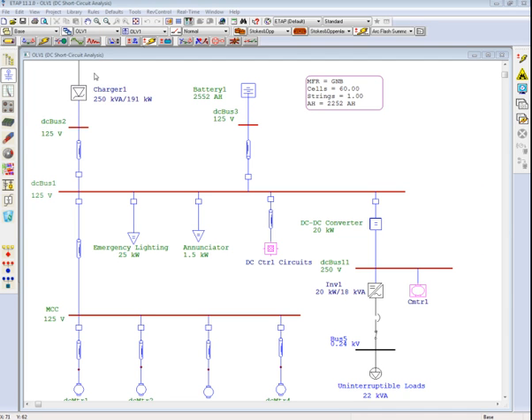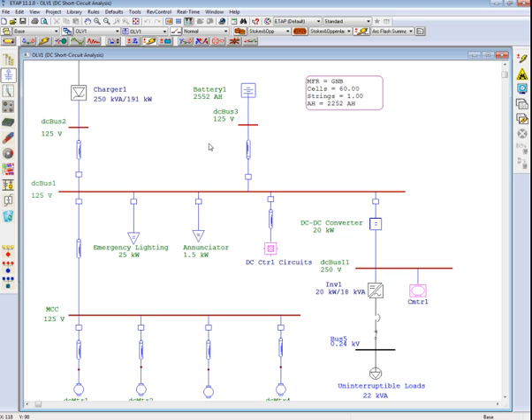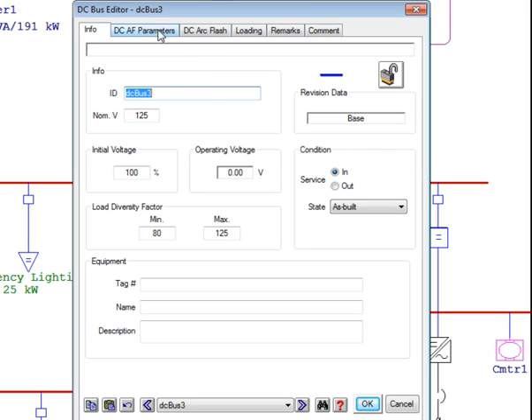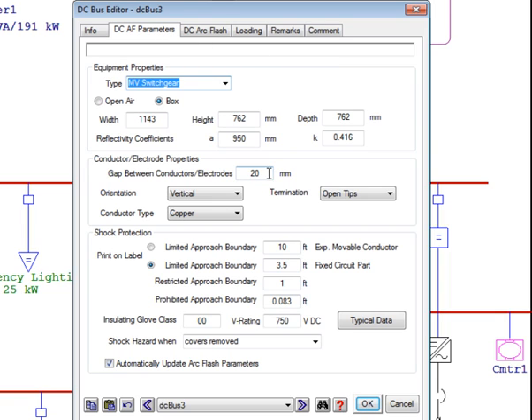How does this apply in ETAP? Going back to ETAP, we now have to consider one more parameter before we can run our analysis — the arc gap between both energized conductors. This parameter can be entered by double clicking on the bus and going to the DC arc flash parameters page. Under the section labeled conductor/electrode properties, there is a field denoting the gap between the conductors or electrodes. In this case, the gap is 20 millimeters.